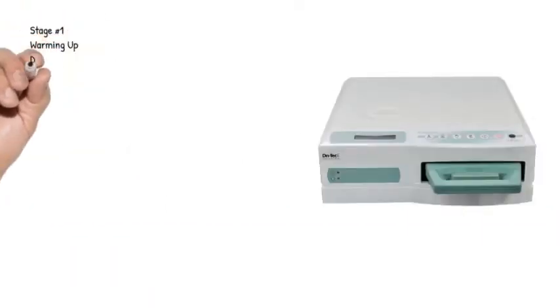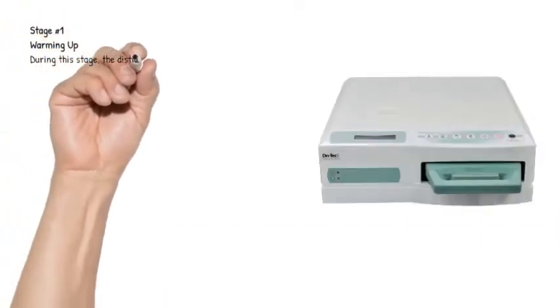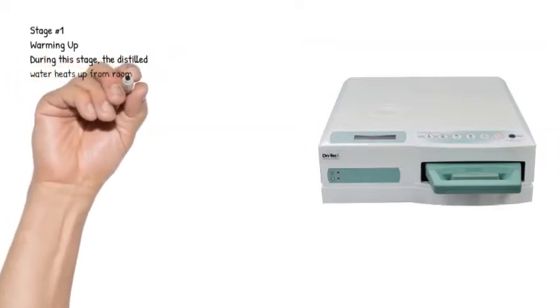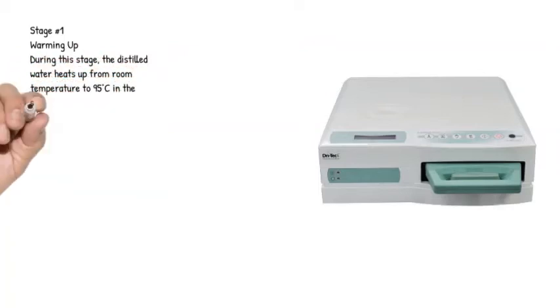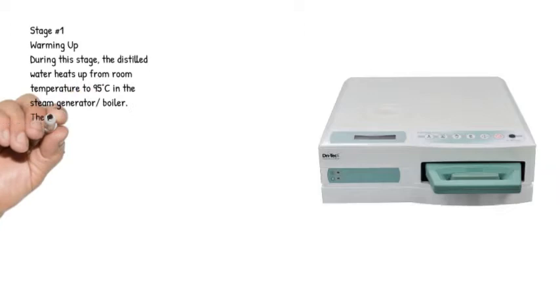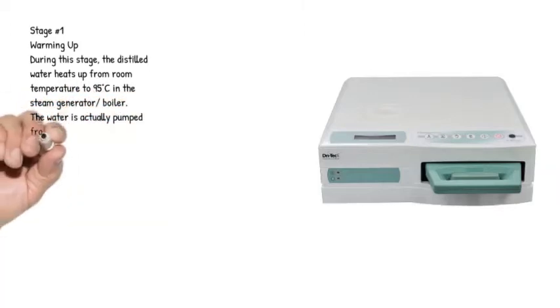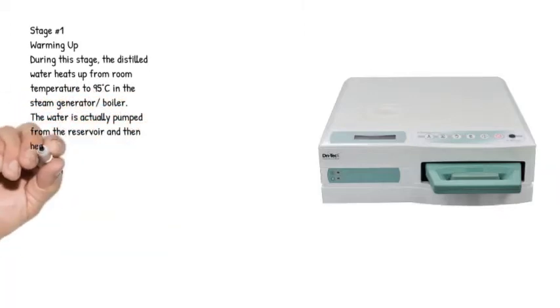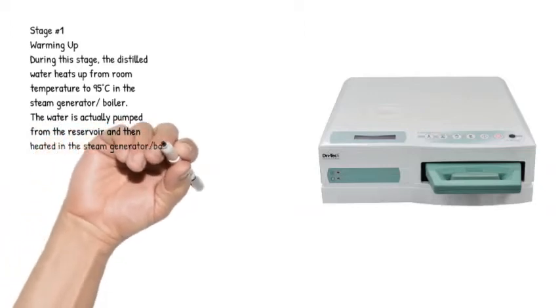Stage number 1. Warming up. During this stage, the distilled water heats up from room temperature to 95 degrees Celsius in the steam generator/boiler. The water is actually pumped from the reservoir and then heated in the steam generator/boiler.